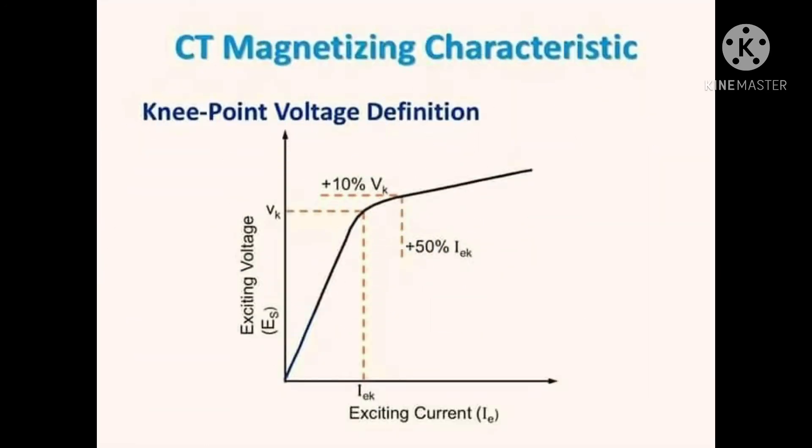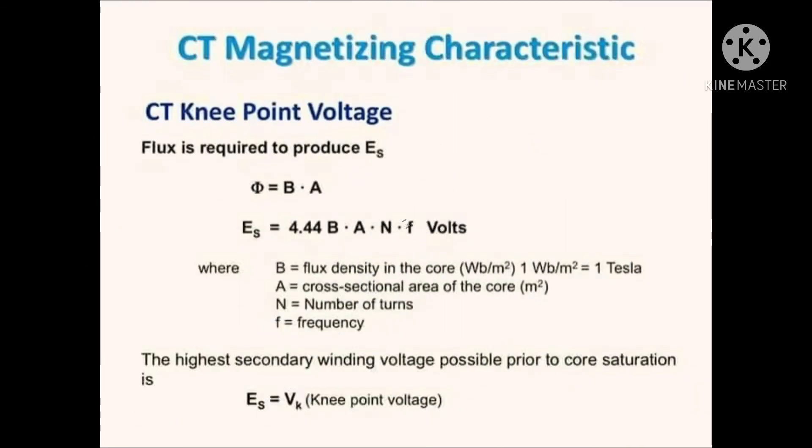The point where CT saturates is also known as the knee point, which according to IEC, is the voltage at which a 10% increase in voltage of CT secondary results in a 50% increase in secondary current. For voltages greater than the knee point voltage, the magnetizing current increases considerably even for small increments in voltage across the secondary terminals.